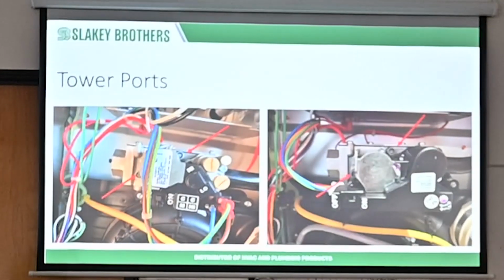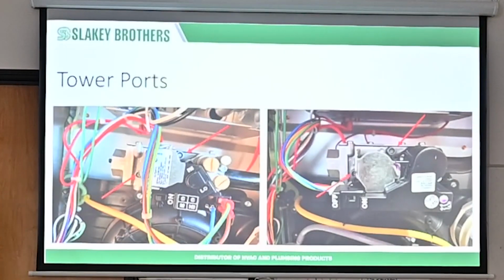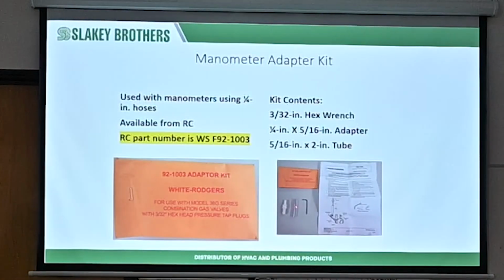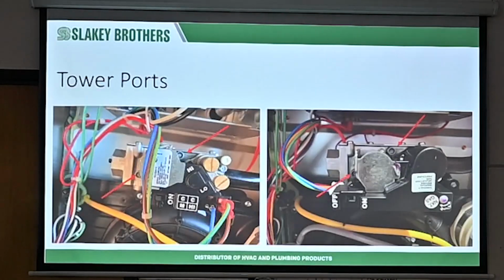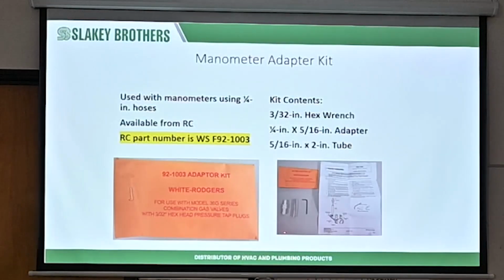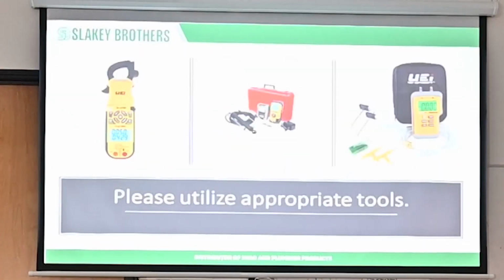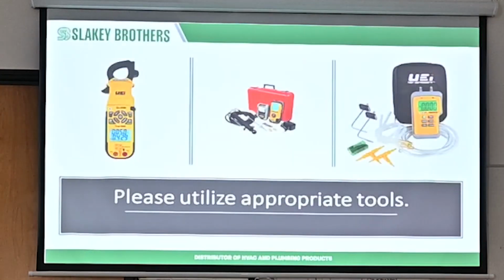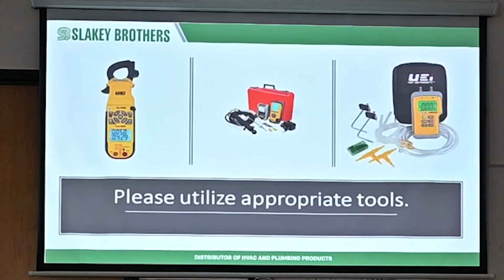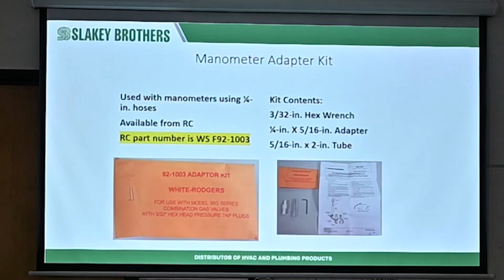Whenever you go check on it, you simply are going to take your little plastic piece here. That goes on the tower port. Then this little piece goes into the top of there, and then that little smaller section, that little 1/4 inch, that's designed for these hoses. So instead of the screw-in right here, you just pop out that little screw-in, and you take these little 1/4 inch hoses, and it attaches right on there, and you're good to go. Makes it a lot easier to check gas pressure with that little adapter.